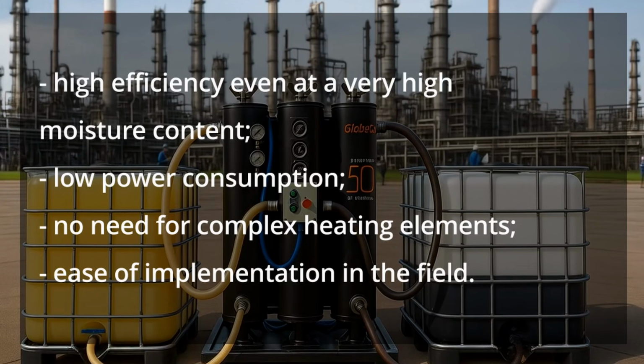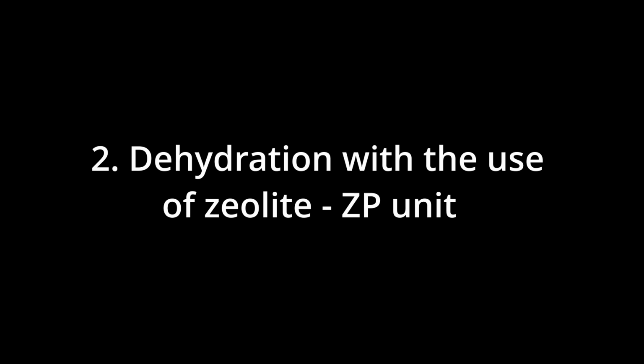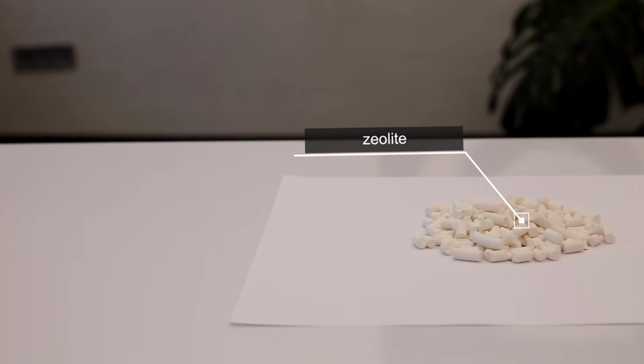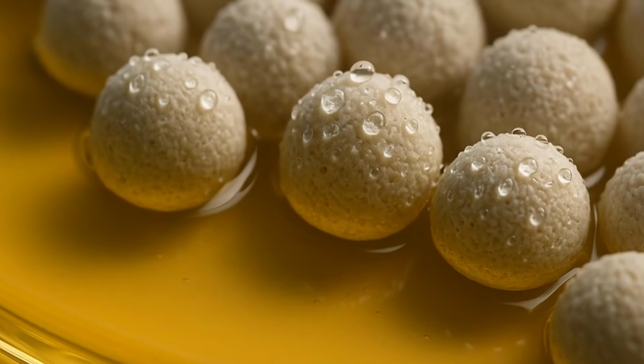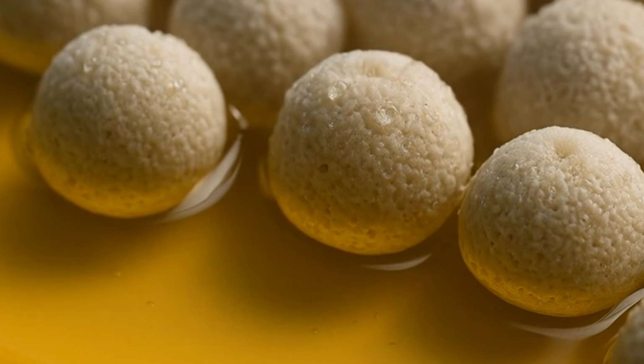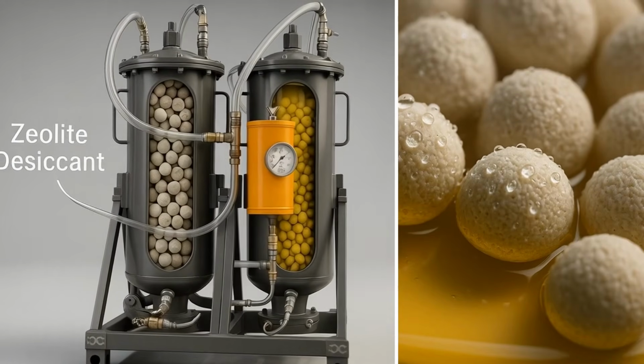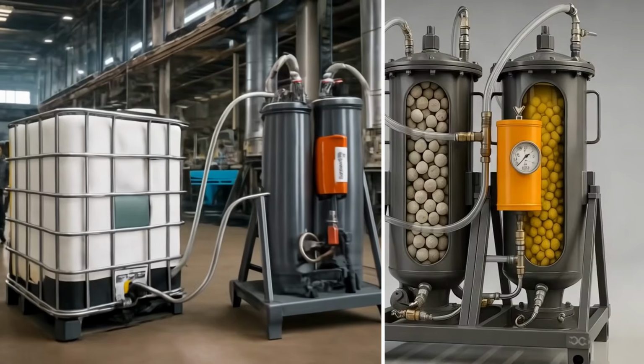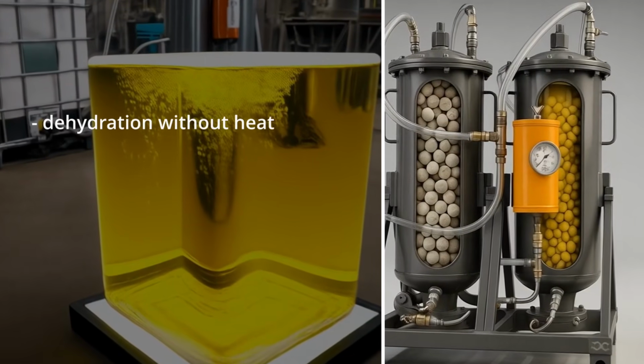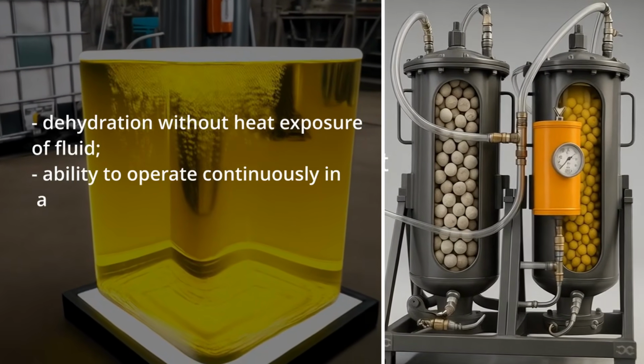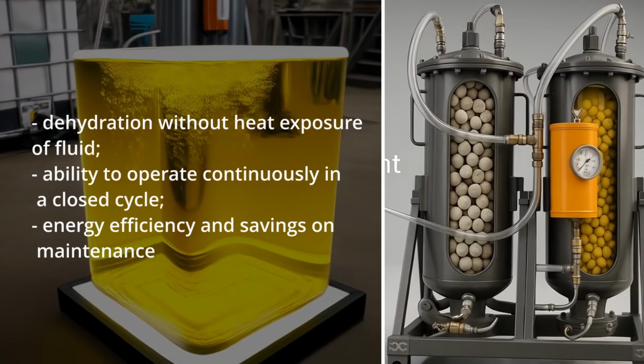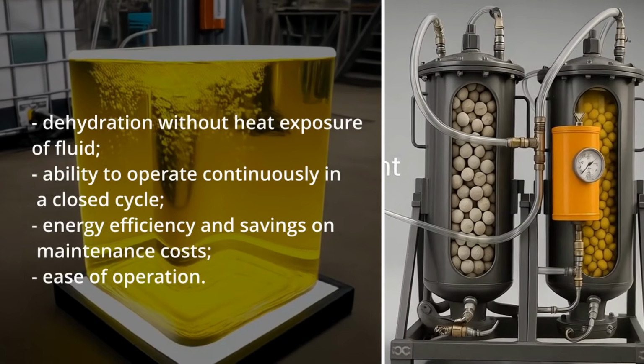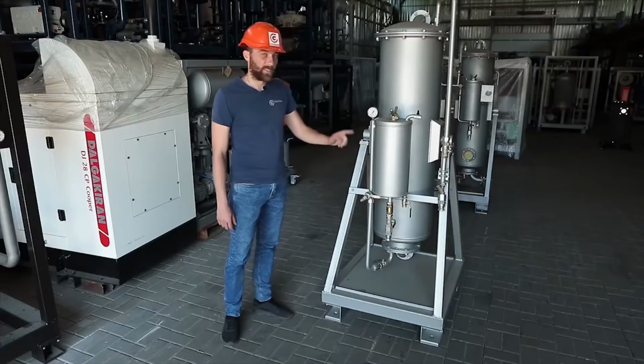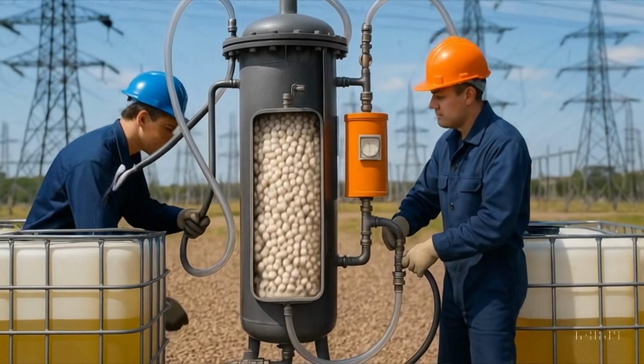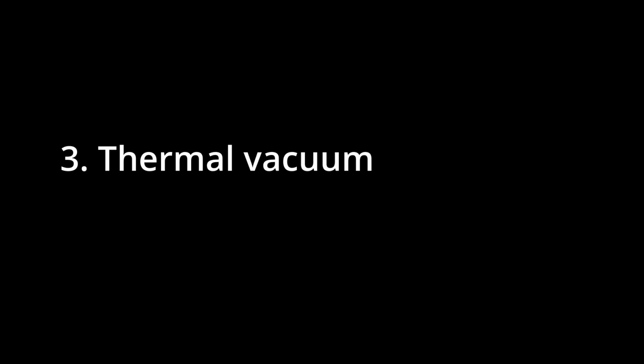2. Dehydration with the use of zeolite-based units. Another option of dehydration is based on the use of a sorbent called zeolite, which thoroughly absorbs moisture from fluids. The sorbent granules reliably retain moisture, as well as can be regenerated with GlobeCore technology and then reused. The main advantages of this technique include dehydration without heat exposure of fluid, ability to operate continuously in a closed cycle, energy efficiency and savings on maintenance costs, ease of operation. This method is particularly efficient during the preliminary dehydration stages, or for maintaining low moisture levels in MIDEL 7131 fluid storage tanks.